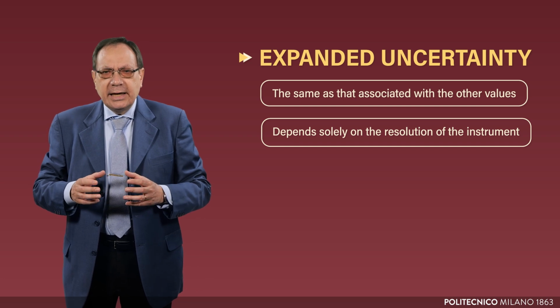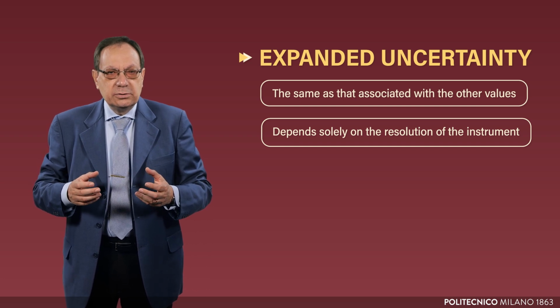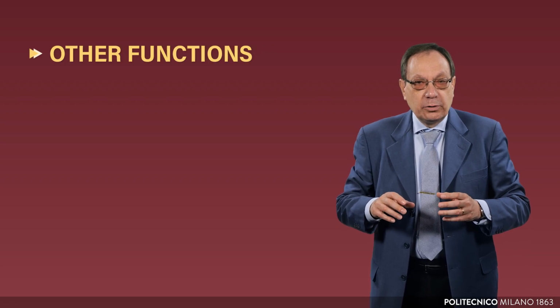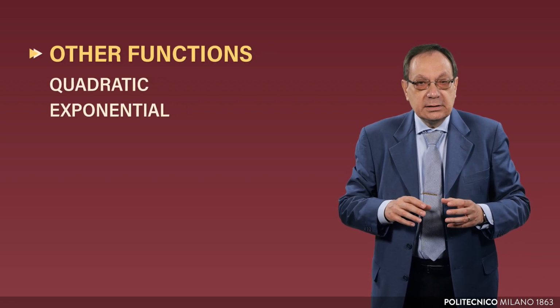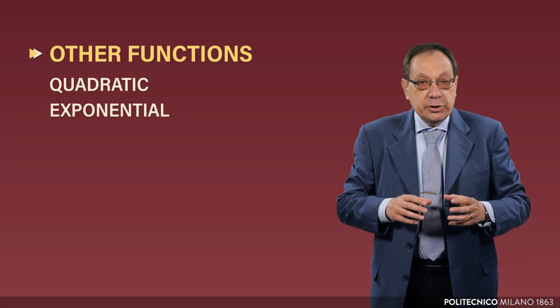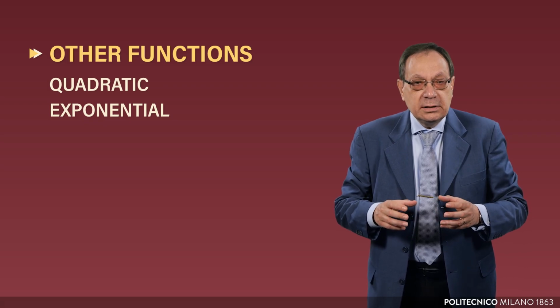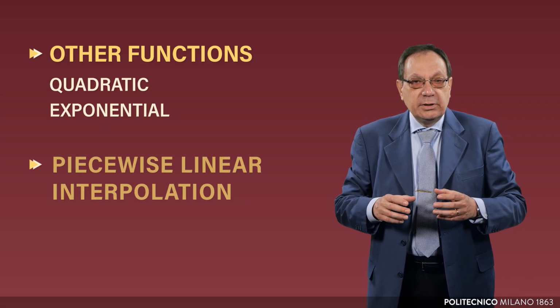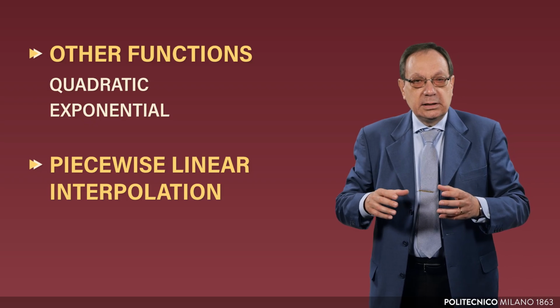In more general cases, interpolation is also used to assess uncertainty. Deviations do not always behave linearly, which is fairly typical for multimeters, but not for other instruments. It is therefore necessary to assess whether they can be interpolated by other functions, for example quadratic or exponential ones, or whether more calibration points need to be considered, and then proceed with piecewise linear interpolations.